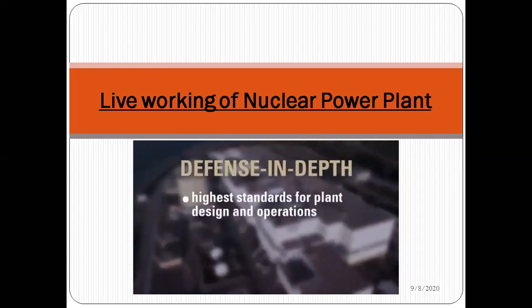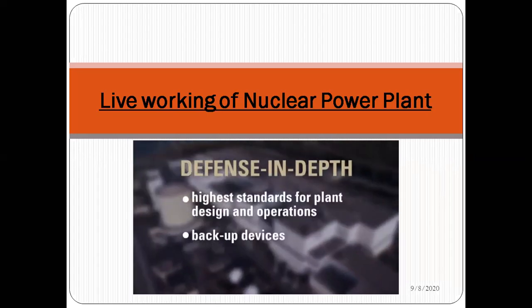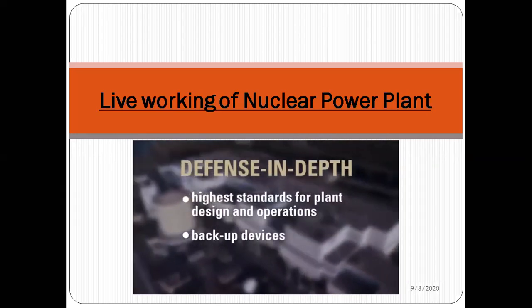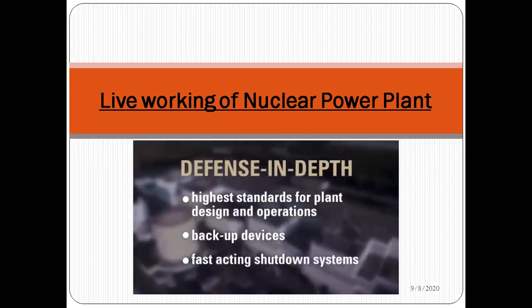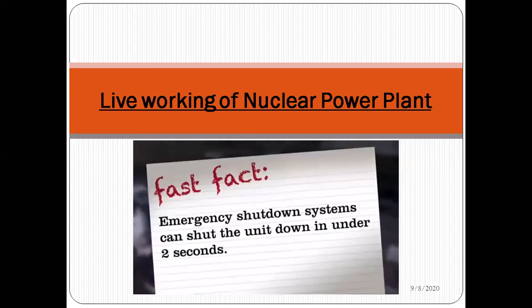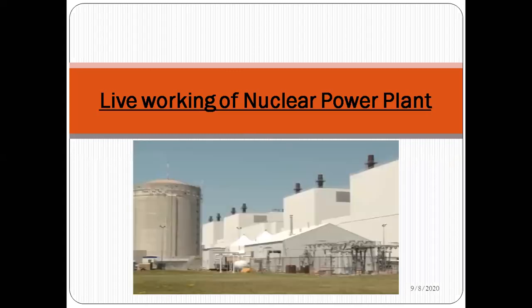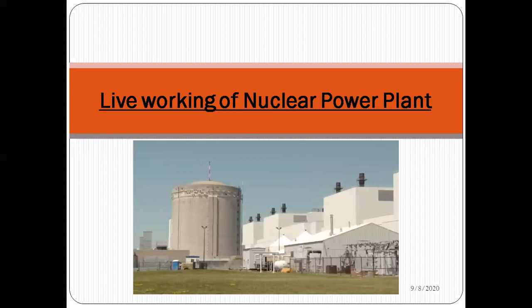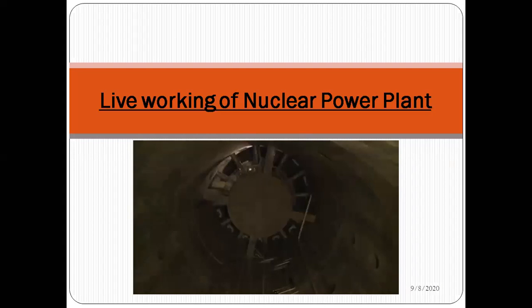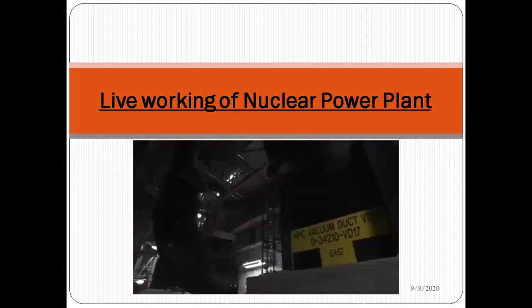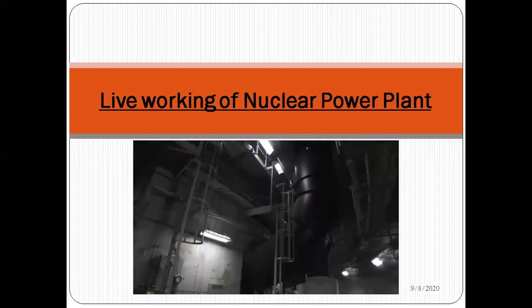The station sets the highest standards for plant design and operations. For critical components and systems, backup devices ensure redundancy at all times, as well as fast-acting shutdown systems. There is a secondary containment structure called the vacuum building - a 71-meter high, 24-story cylindrical concrete structure connected to the reactor buildings by a pressure relief duct. This is a unique safety feature of the CANDU system.